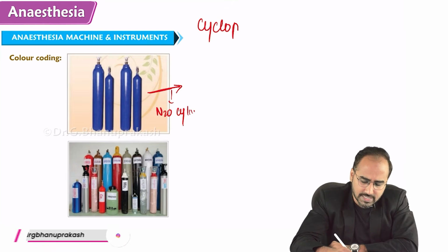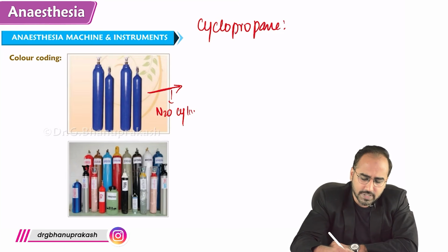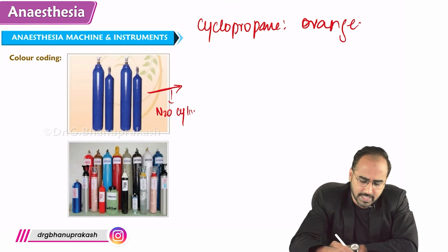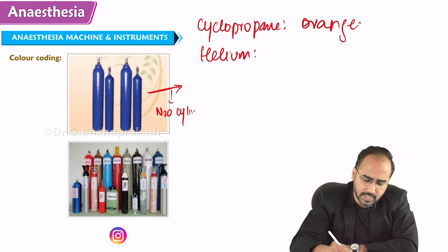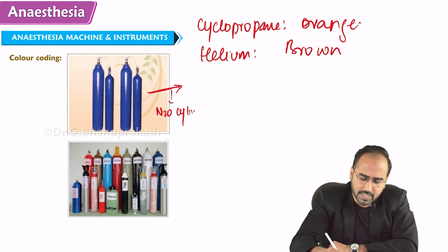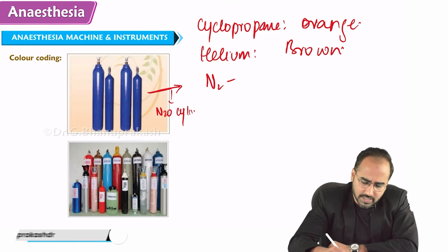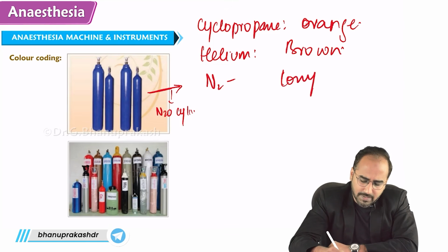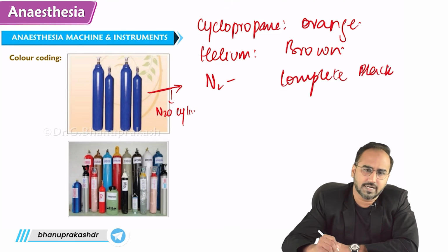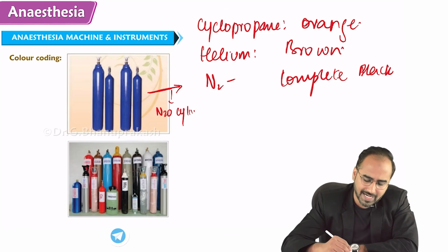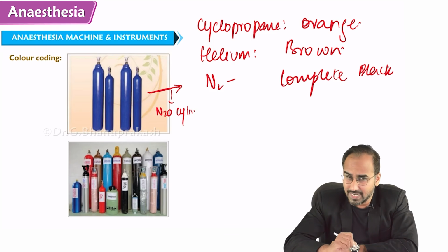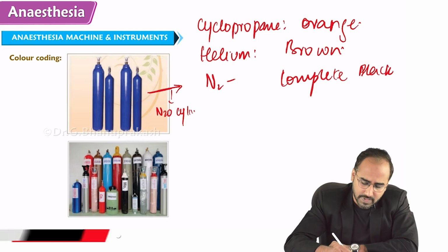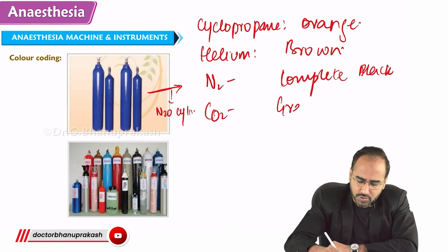There is a gas called cyclopropane. The color coding for cyclopropane is orange. It is stored in an orange cylinder. Helium is stored in a brown cylinder. Nitrogen is stored in a completely black cylinder. Cyclopropane is done, helium is done, nitrogen is done. Carbon dioxide is stored in a grey cylinder. This you have to remember.